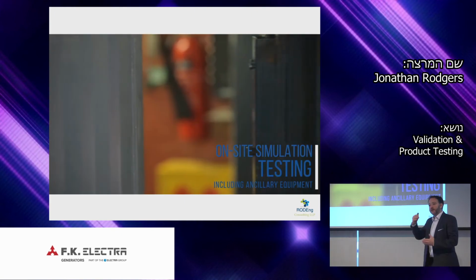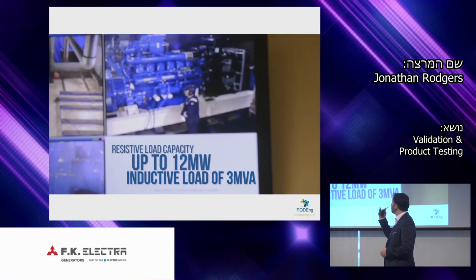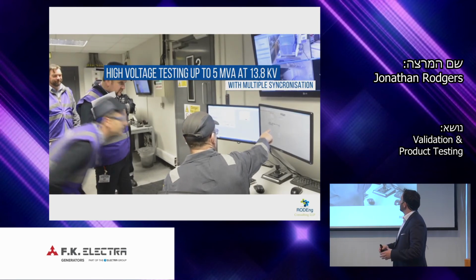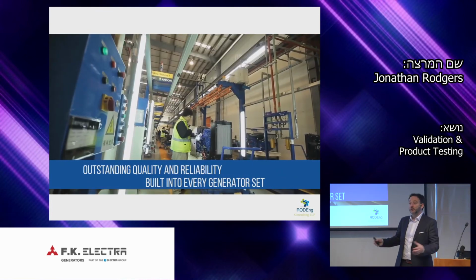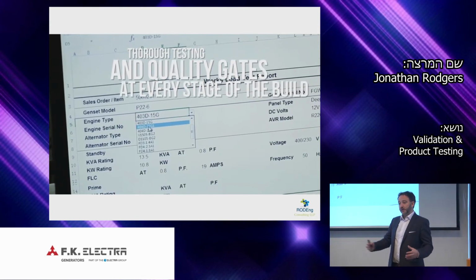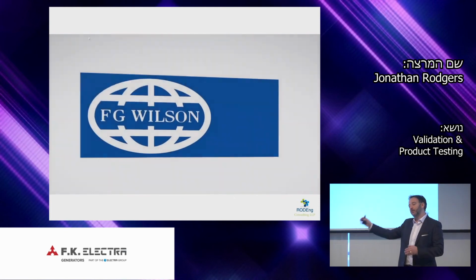Every generator is then tested to a specific set of test requirements through our test cells. These are the test cells that Robert and I would have worked in, the bespoke larger test cells in Larne, Bay F. These are for factory witness tests or for testing very bespoke generator applications. What this does is develop a test method for us to employ everywhere globally that we manufacture generators. So the tests that we carry out at the bottom of Bay D in Larne are the same tests that we have in our China facility.